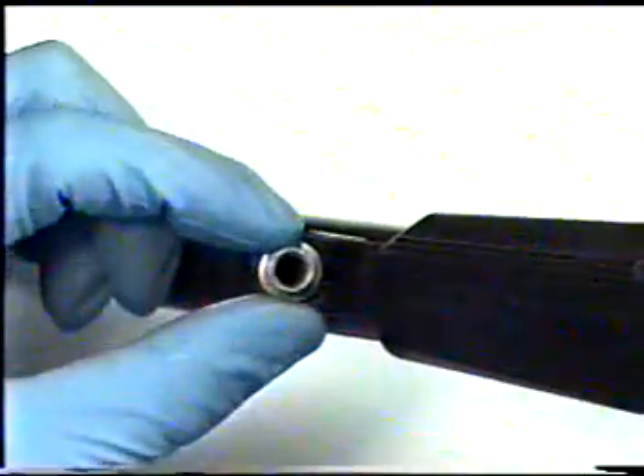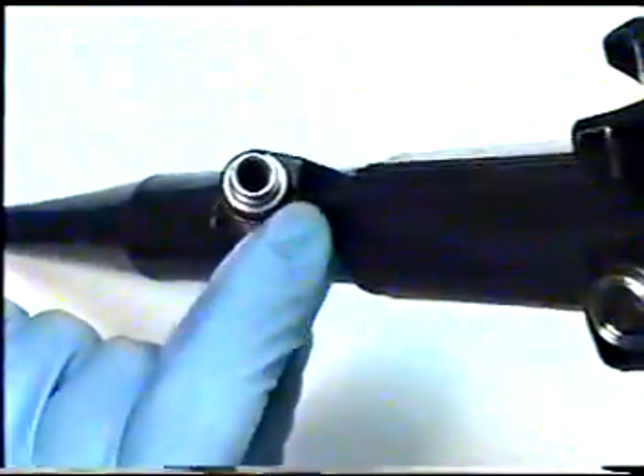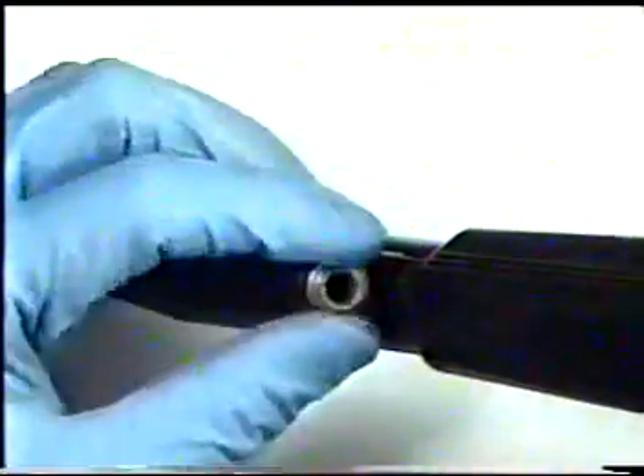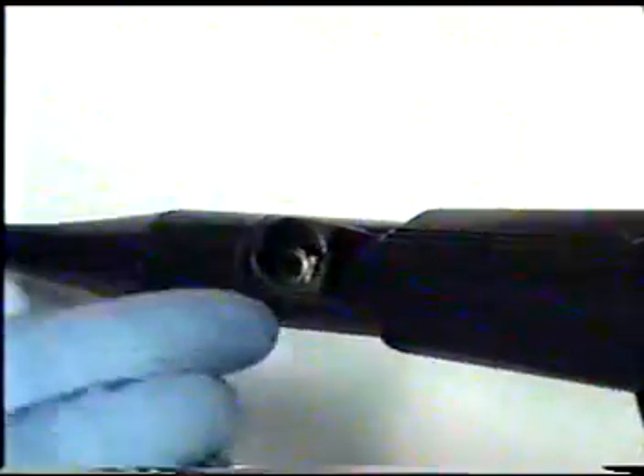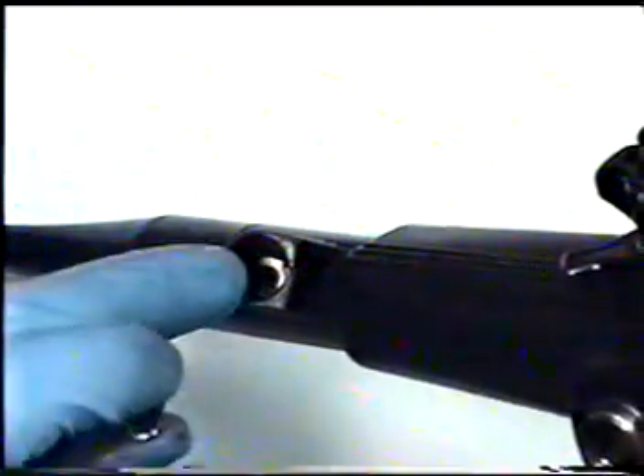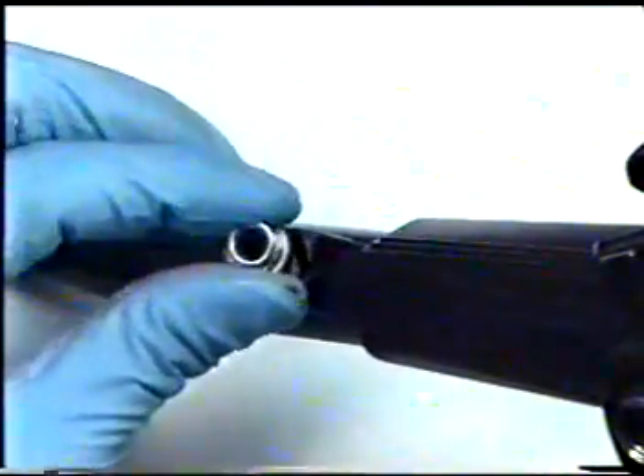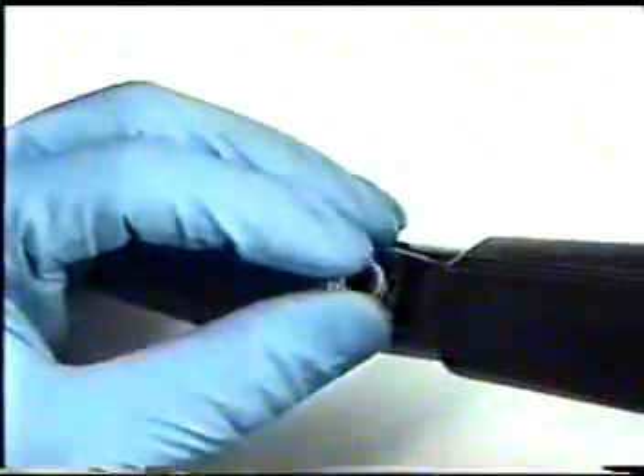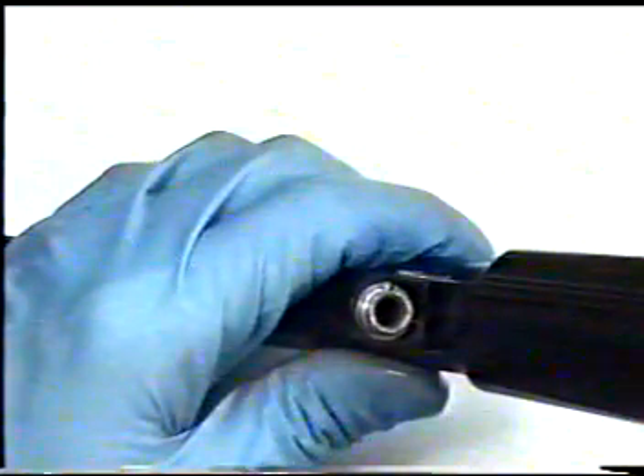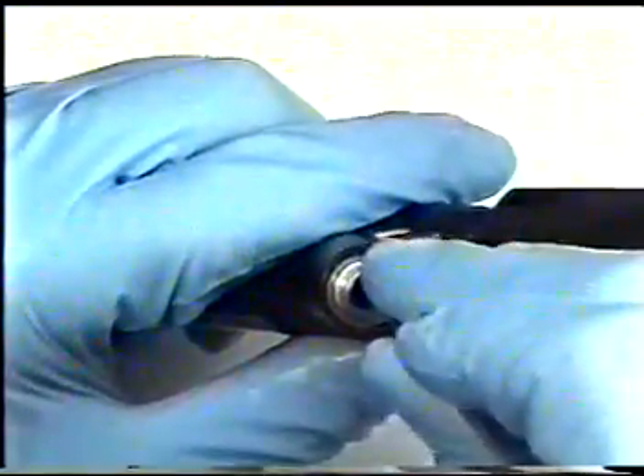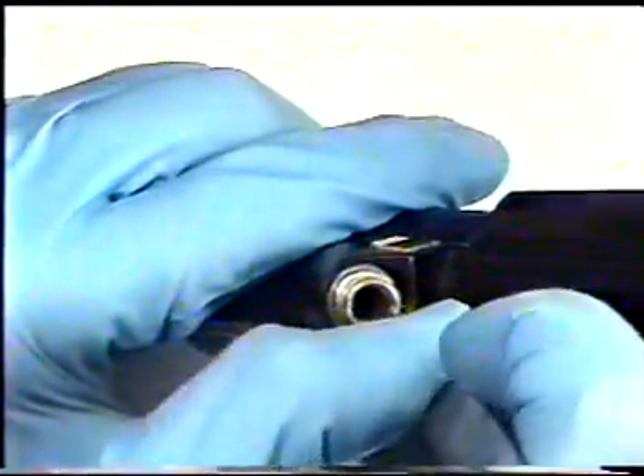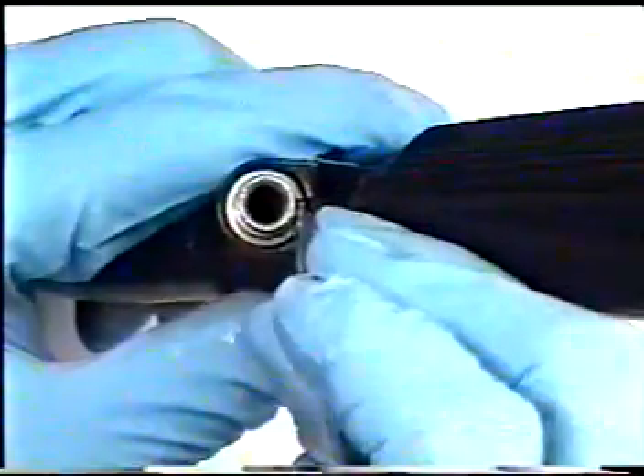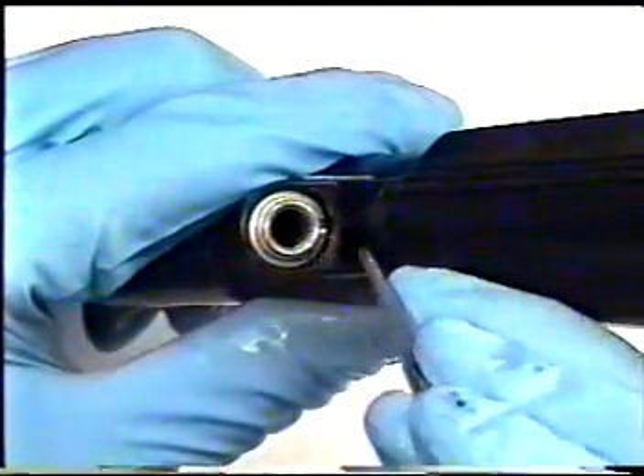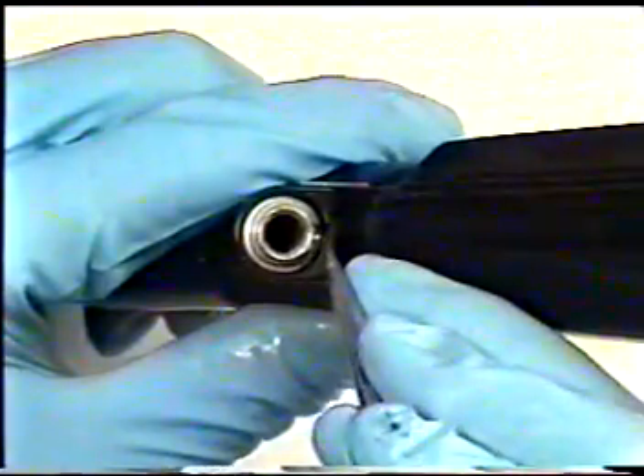Apply this piece at a 90-degree angle in reference to the locking key opening, pushing down with your thumb, also being sure that you are not kinking any wires or light guides or image bundles when applying this piece. Push down with your thumb. Utilizing your tweezers, turn this ring again 90 degrees to meet the slot for your biopsy housing key ring.